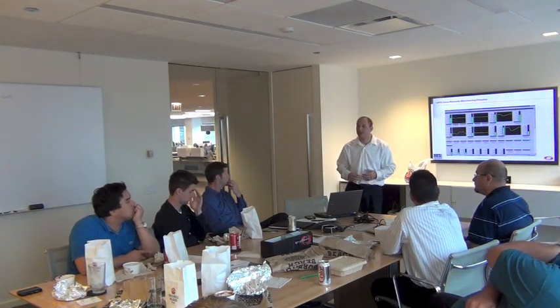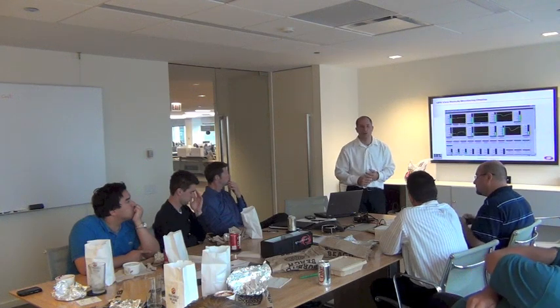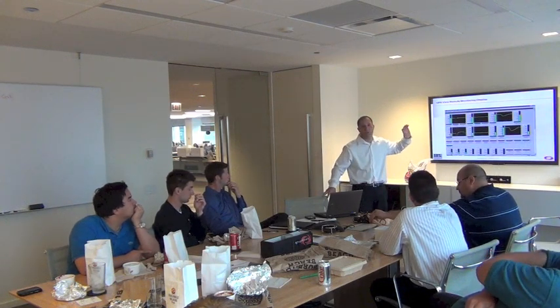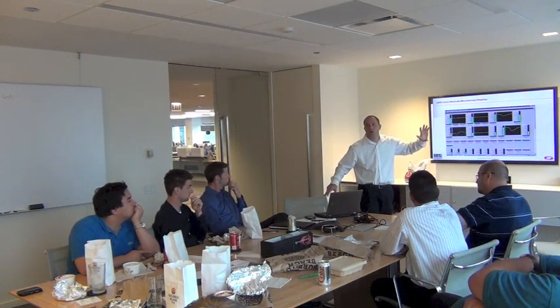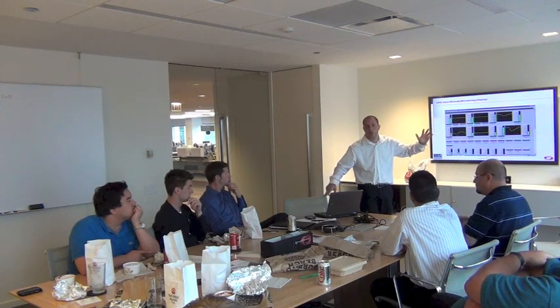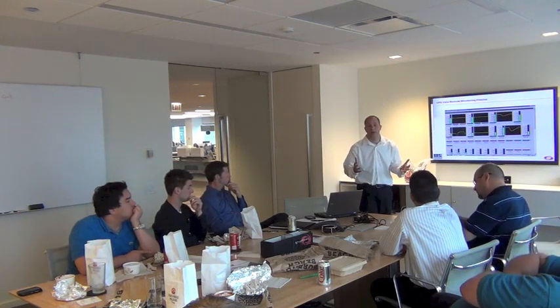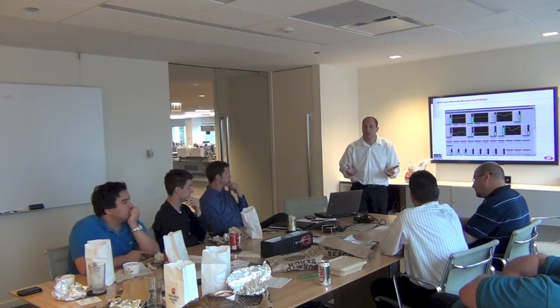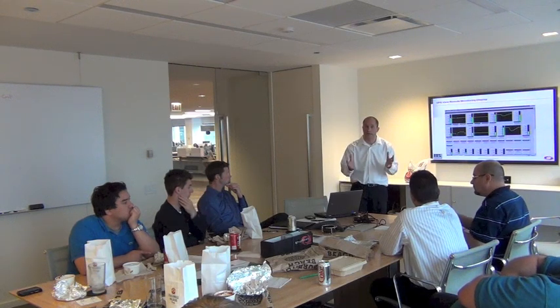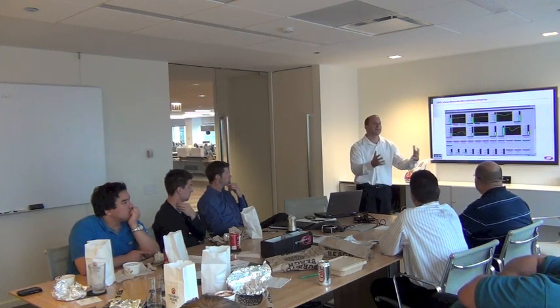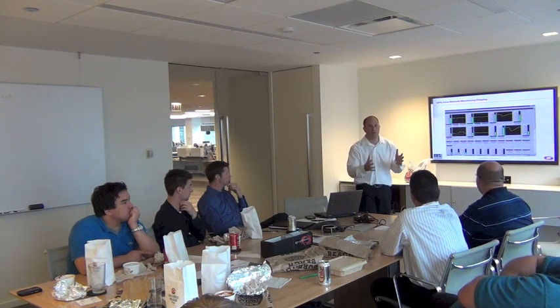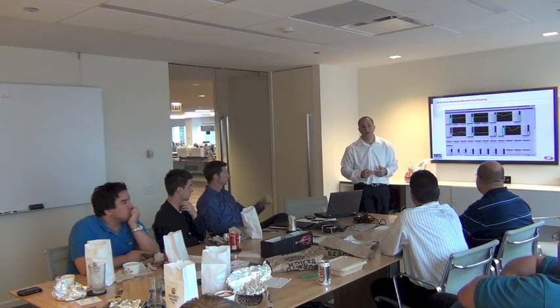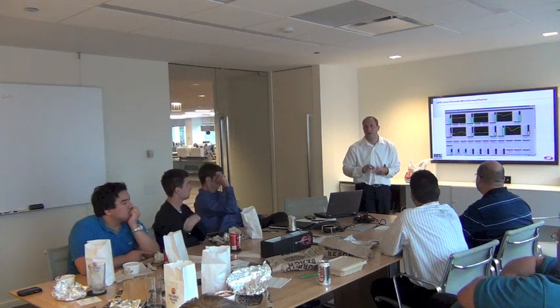So there's lots of nice integration features with this software. And one of the biggest advantages with our UPS, especially on the battery-free side, is we have over 100 patents that are really critical and have really enabled us to have a really nice integrated solution. That's a huge advantage to us in the field. We really end up with a UPS that's designed to be used with flywheels versus a UPS that's really designed to be used with batteries and you're putting flywheels on it, because there's lots of integration advantages that we get with our equipment that our competitors don't.